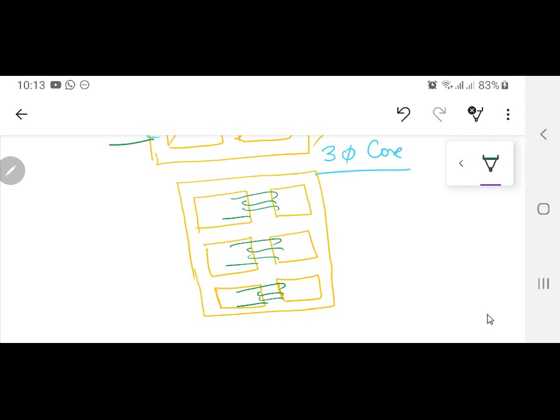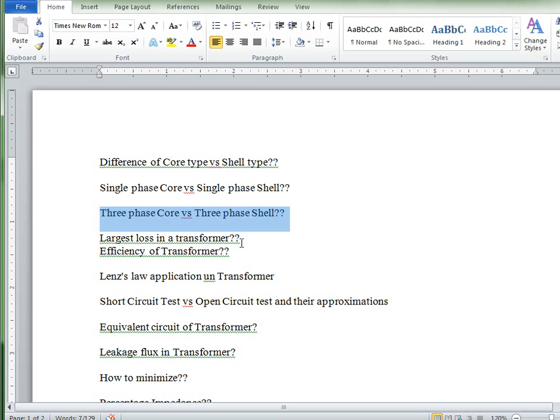So you can see in a shell type transformer, this is a 3-phase shell type transformer. 3-phase shell types are not normally used in distribution transformers. The reason is they can't be cooled down very well, because distribution transformers have to work 24 hours a day. You can't cool them down very efficiently. So you won't find them there; they are only used in power transformers because maybe they are connected with a Tarbela dam or a Mangla dam generator, and that generator is only going to provide for maybe 7, 8 or 10 hours, and then afterwards it's going to cool down. So shell type transformers are not normally used over there.